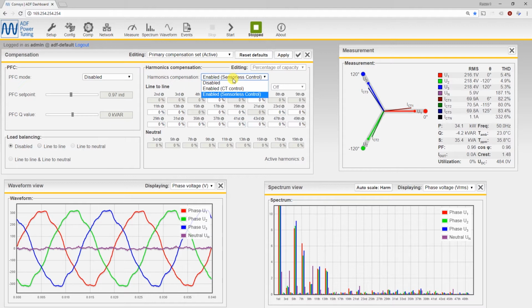There's a small difference in how the active filters are configured. In current control and CT control, the settings that we write here is the degree of compensation. In sensorless control, it is actually the percentage of capacity. The degree of compensation can't be used for sensorless control, because we would always need to know what is 100%. In sensorless control we miss this information. The information what is 100% of the voltage distortion gets lost in the process of compensating. In current control we always have that information available. So that means in sensorless control our target level is always 0% distortion on a single harmonic.